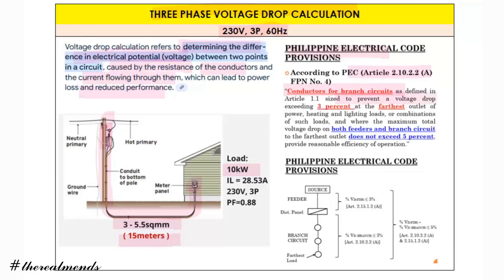The PEC provision states that conductors for branch circuits shall be sized to prevent a voltage drop exceeding 3 percent at the farthest outlet for heating, lighting loads, or combinations thereof, where the maximum total voltage drop on both feeders and branch circuits to the farthest outlet does not exceed 5 percent. So from the source to the distribution panel, the allowable voltage drop is 2 to 3 percent.